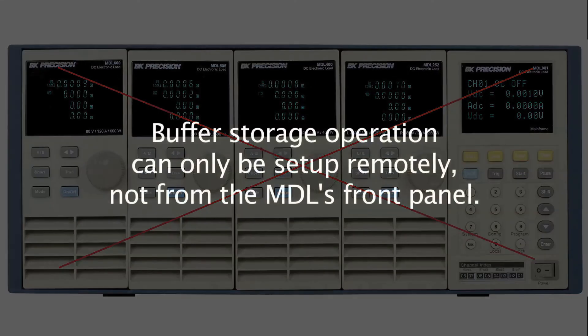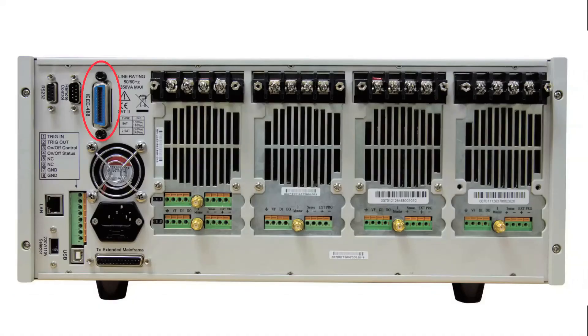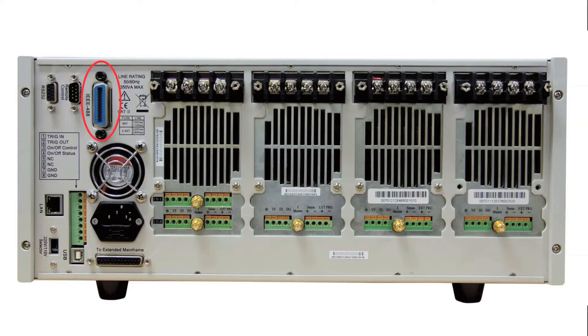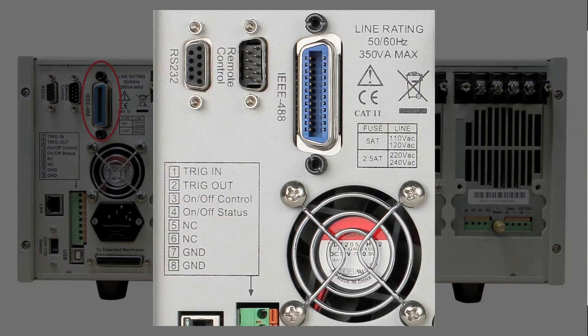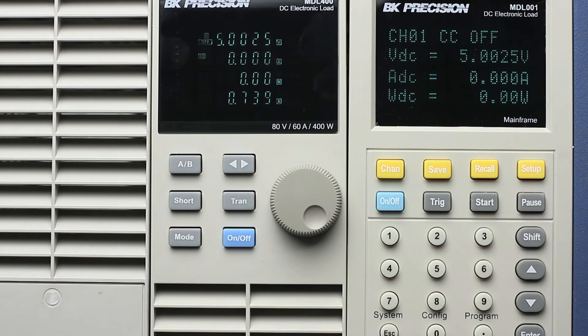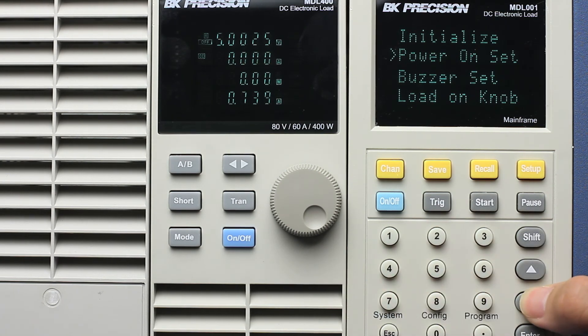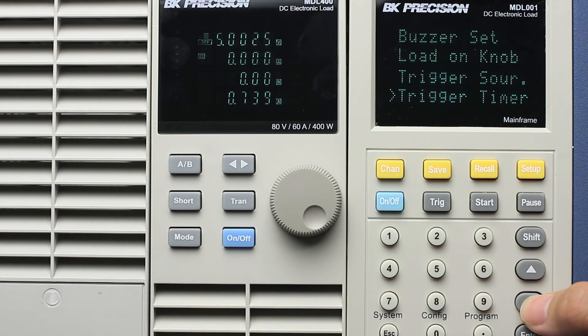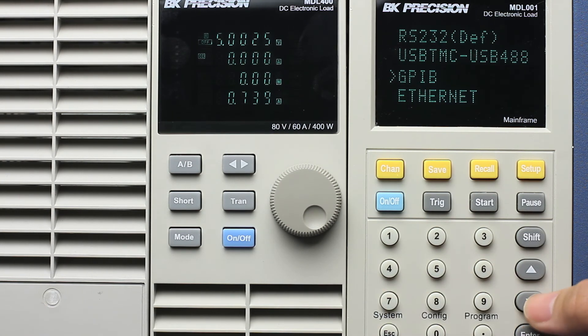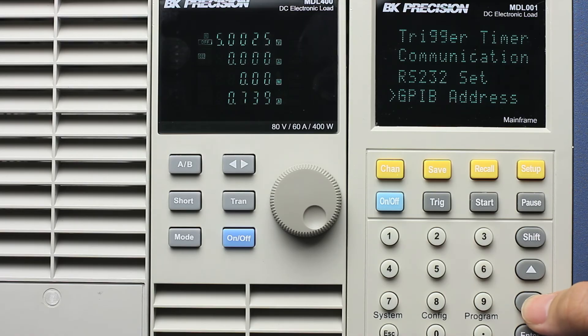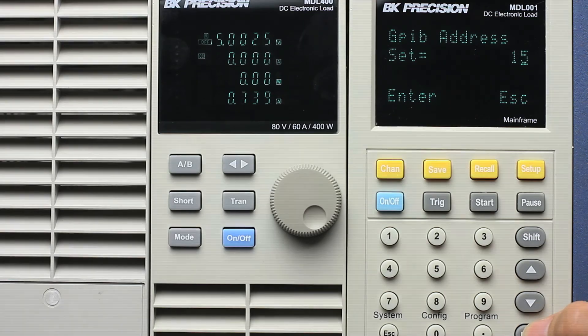Buffer storage operation cannot be set up from the front panel. All of the setup and initialization is done remotely. In this video, I will be using the GPIB interface to configure the DC load for buffer storage operation. For convenience and demonstration, I will use LabVIEW software to show you how it works. The first thing we need to do is select GPIB as the interface for remote communication.